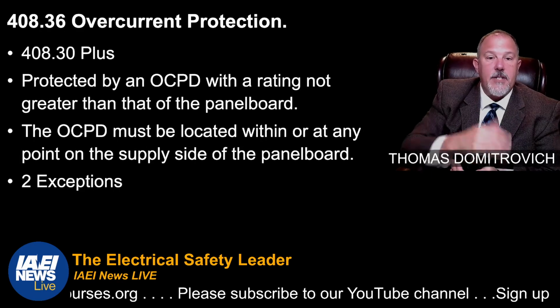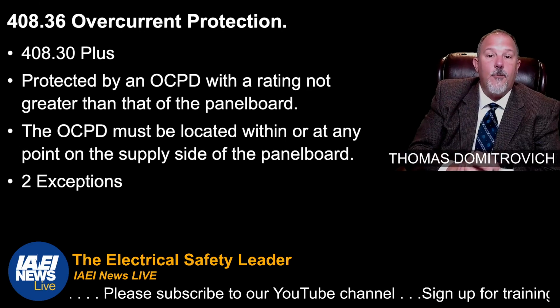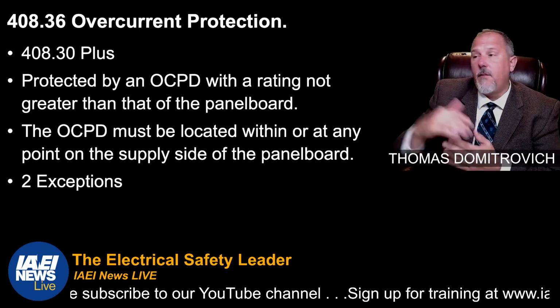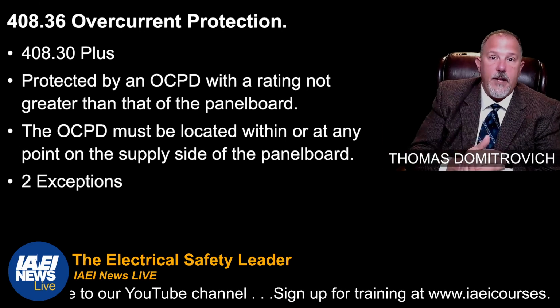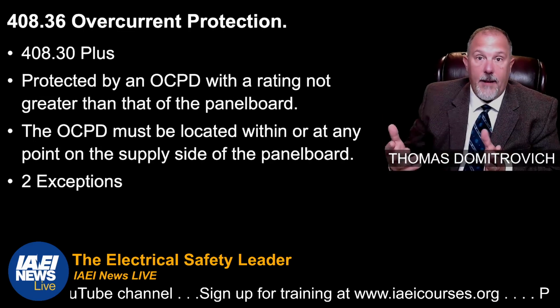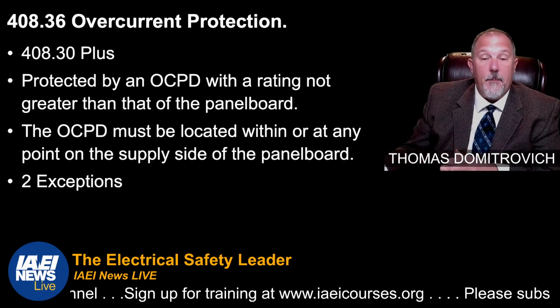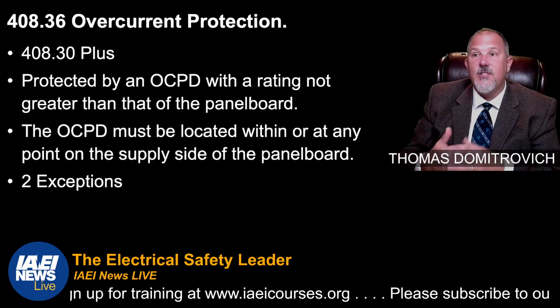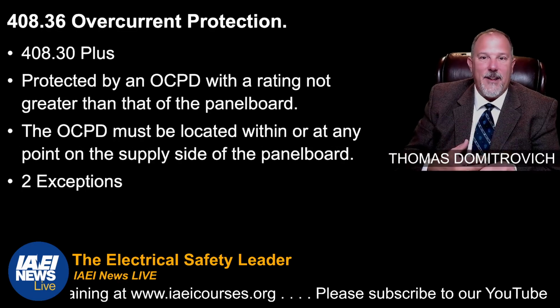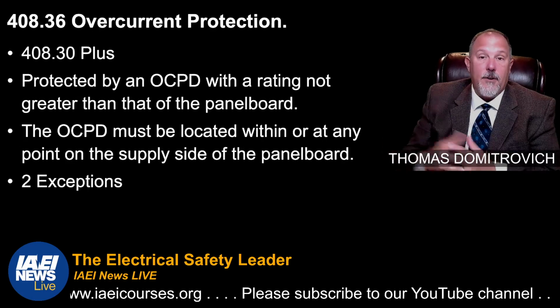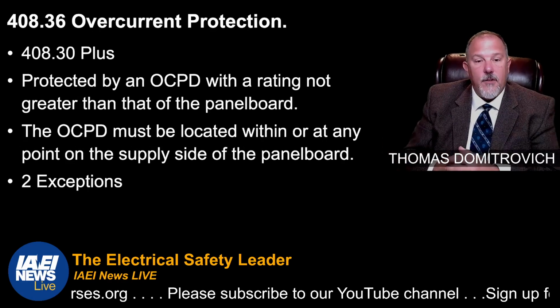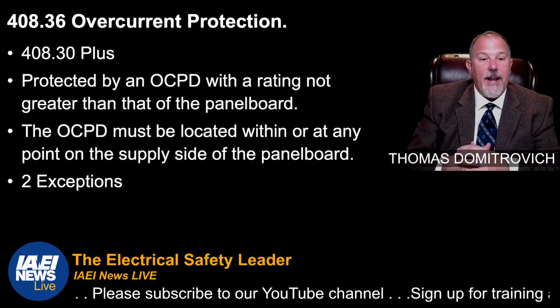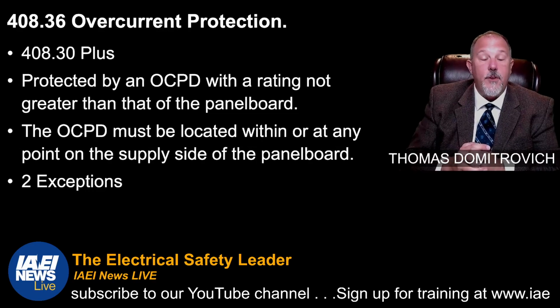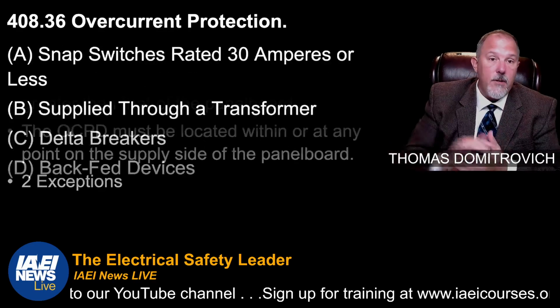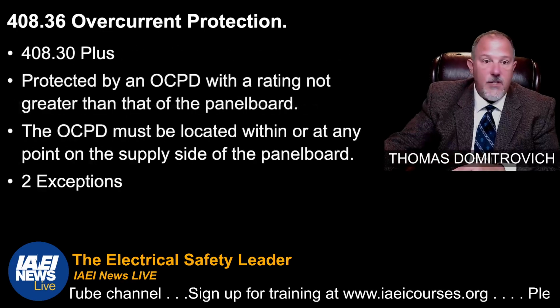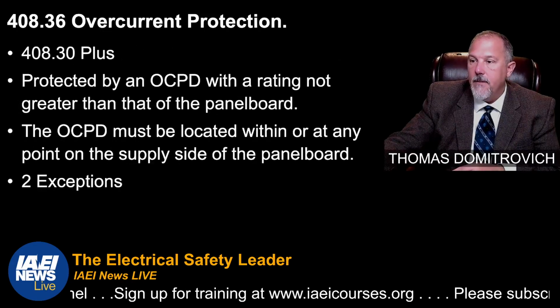408.36 says that you have to be protected by an overcurrent device rated not greater than that of the panel board. So if you have a 400 amp panel, you need a 400 amp device. You can't be greater than that. You can put a 200 amp overcurrent device feeding a 400 amp panel, but you can't put a 600 amp or an 800 amp overcurrent device feeding a 400 amp panel board. The overcurrent device must be located within or at any point on the supply side of the panel board. There are 2 exceptions, and these are important because a lot of people miss these 2 exceptions in 408.36.